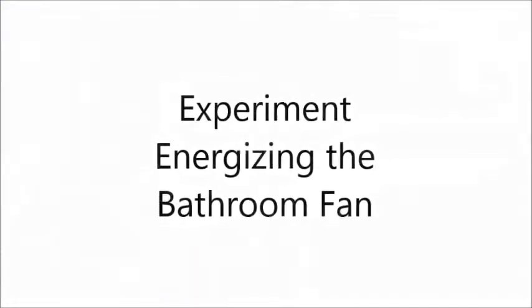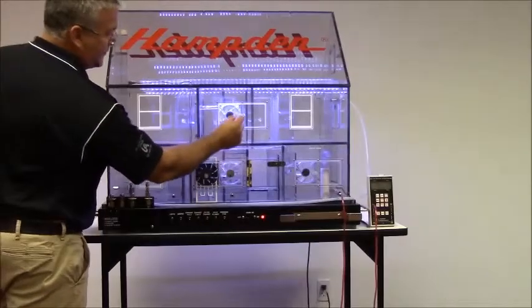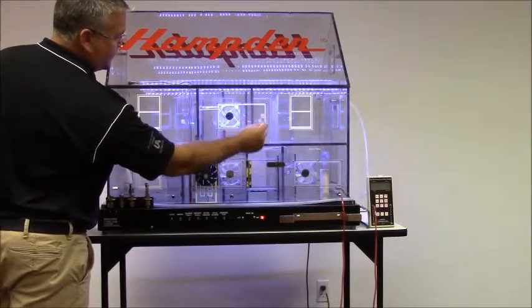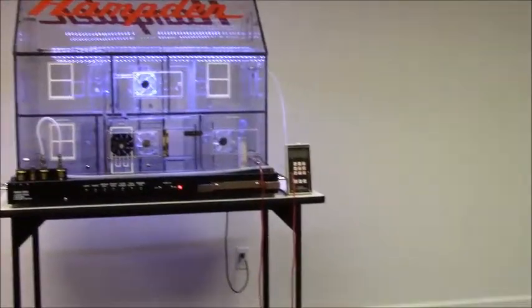What this test shows is that with all interior doors open and exterior doors closed, the HVAC blower creates a slight depressurization in the utility room with reference to outside. By energizing exhaust fan 2, you can see that something as simple as a bathroom fan will create a negative pressure of 10 pascals with reference to outside.